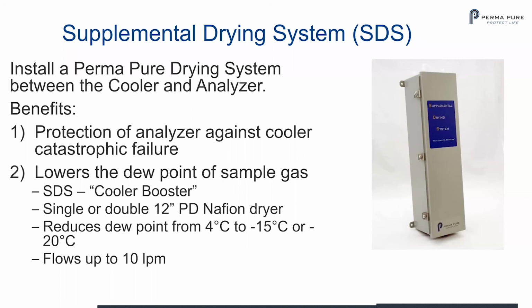So you reduce the dew point from 4 to -15 or -20 degrees. It provides a lot of those reliability benefits that I was explaining before, why you can use this and not have to use a cooler. This makes certain that if your cooler fails, you always have that last chance drying. These dryers can handle the volume and you won't get a destroyed analyzer. Secondly, you're reducing the amount of water to the point where the water doesn't recombine with those other components to form acids that later on condense on the optical bench.